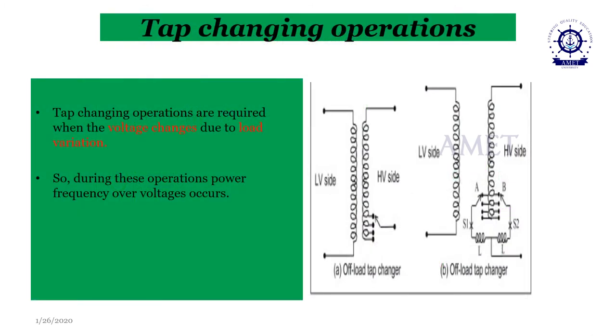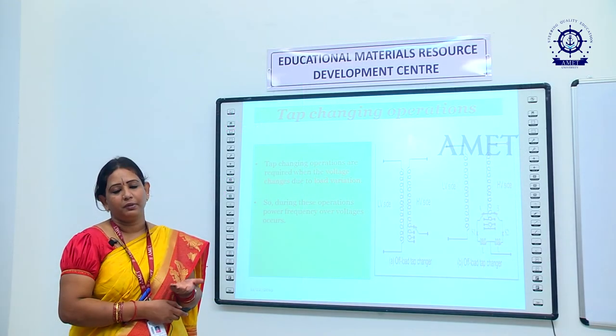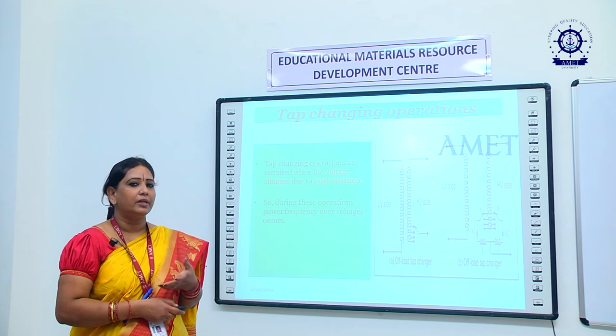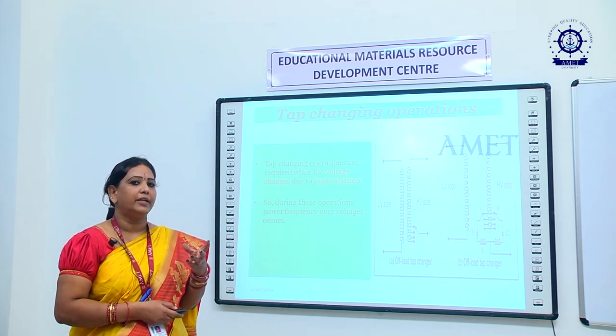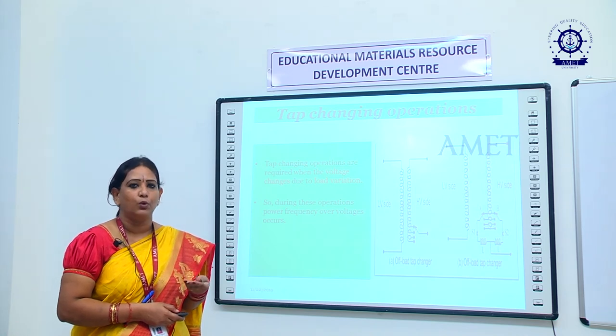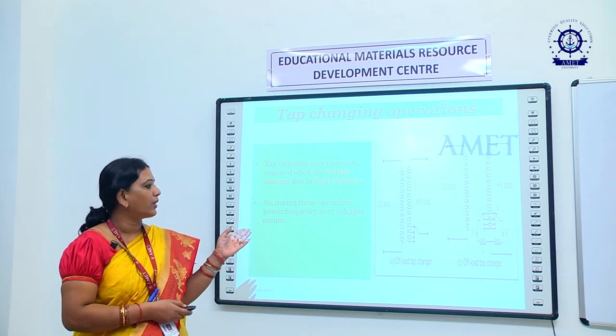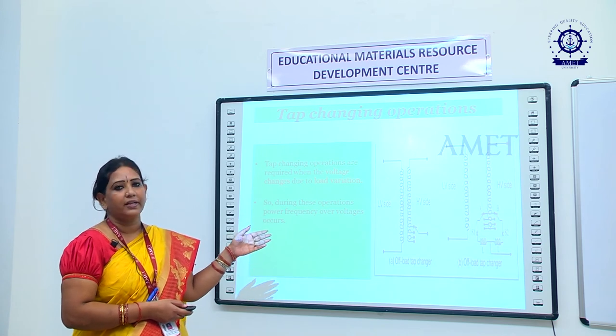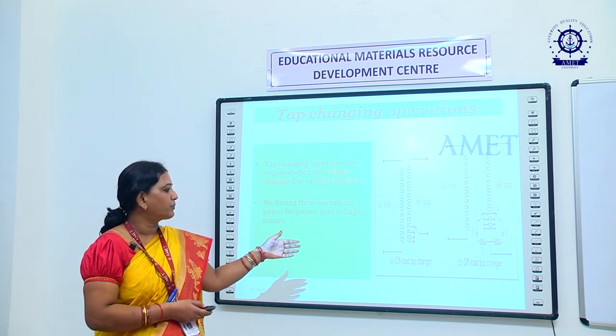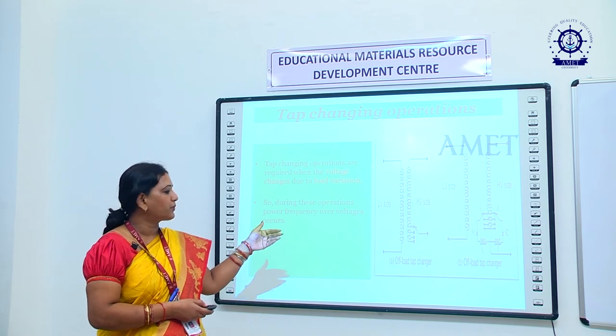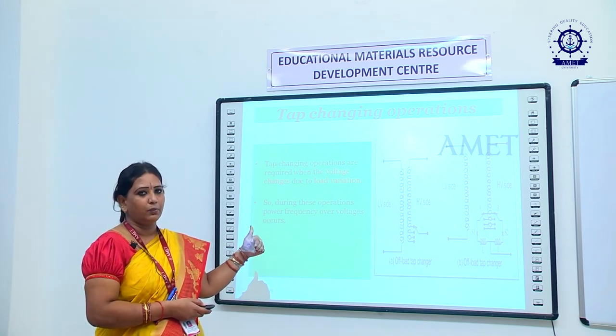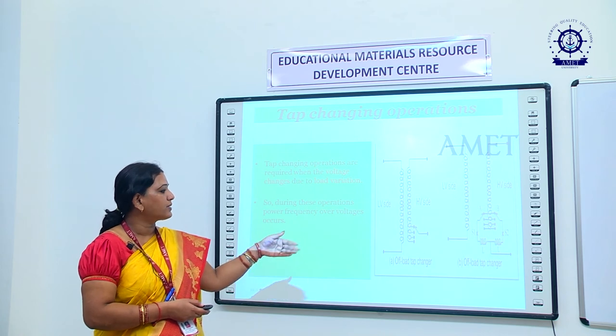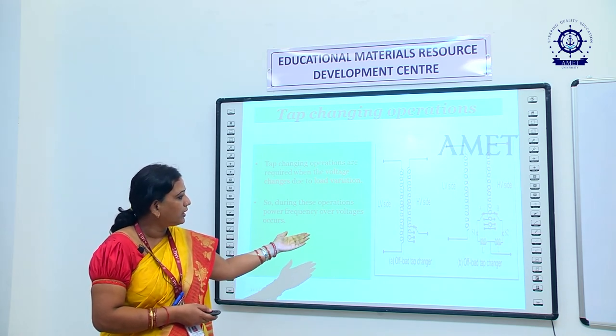This slide explains the tap changing operations, because if we want to change the voltage for any application, we will be in a situation to vary the taps. Increasing the number of taps represents an increase in voltage. The taps can be provided on the primary side or on the secondary side. Here this is called an offload tap changer. Offload means the taps are changed when the supply is cut out.